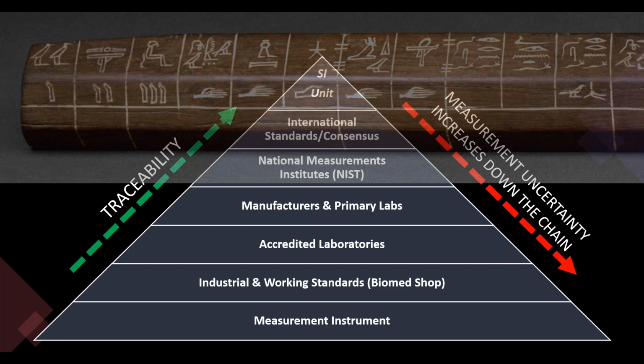And I'll give you guys a great example too. I know a lot of shops will think, oh, that's got to be a really expensive, sophisticated piece of equipment. Number one, we don't sell this, so this is not a plug for the equipment, okay? It's a Keithley DMM 6500 6.5-digit bench meter with the digitizing properties. The retail value is $1,200. The probe plugged into it is a PRT, a high accuracy probe that's about $450.